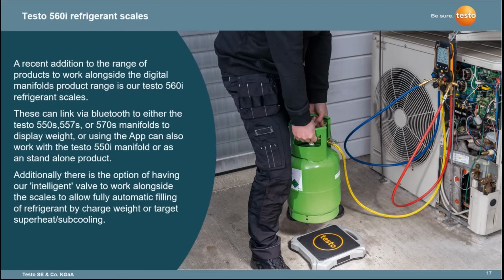Also, with the scales, we have an option of just the scales, or you can buy a scales and intelligent valve combination. And with the intelligent valve, what that actually allows you to do, with the manifold or the app, is set a target charge weight or a target superheat value. The intelligent valve will actually allow the refrigerant to flow into the system to achieve a target weight or a target superheat. So it automates the actual charging process. So you have the ability to basically dictate what the charge weight is that needs to be added into the system, or a target superheat value. The intelligent valve is basically controlled again via Bluetooth from the manifold or the app, and it effectively will automate the process of adding refrigerant into the system to obtain that charge weight or target superheat.